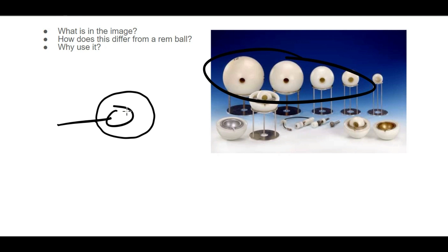Different spheres have different energies; they moderate the neutrons at a different rate, and that's where this term rem ball comes in. A rem ball is just a Bonner sphere that is 10 to 12 inches. With a 10 to 12 inch sphere, we can directly measure the dose equivalent.